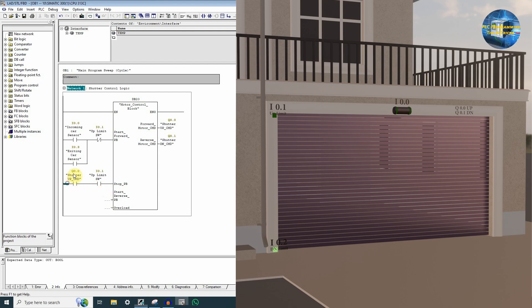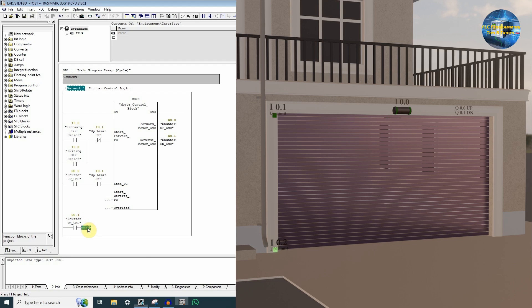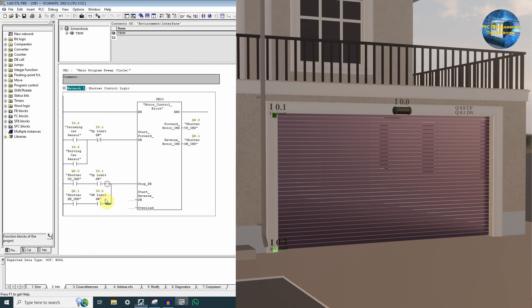The same thing we have to write while the shutter is closing. We will insert another contact and assign it Q0.1, which is the shutter close command, and in series with it we insert a normally open contact of I0.2, which is the down limit switch, and connect it in parallel. So whether the shutter is opening or closing, once these limit switches are activated, the shutter motor will stop.